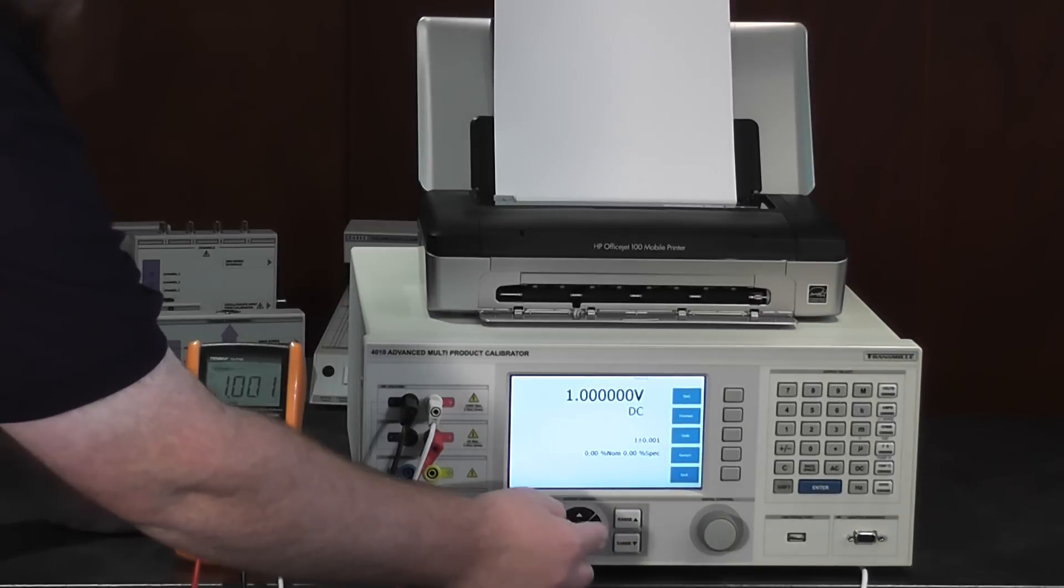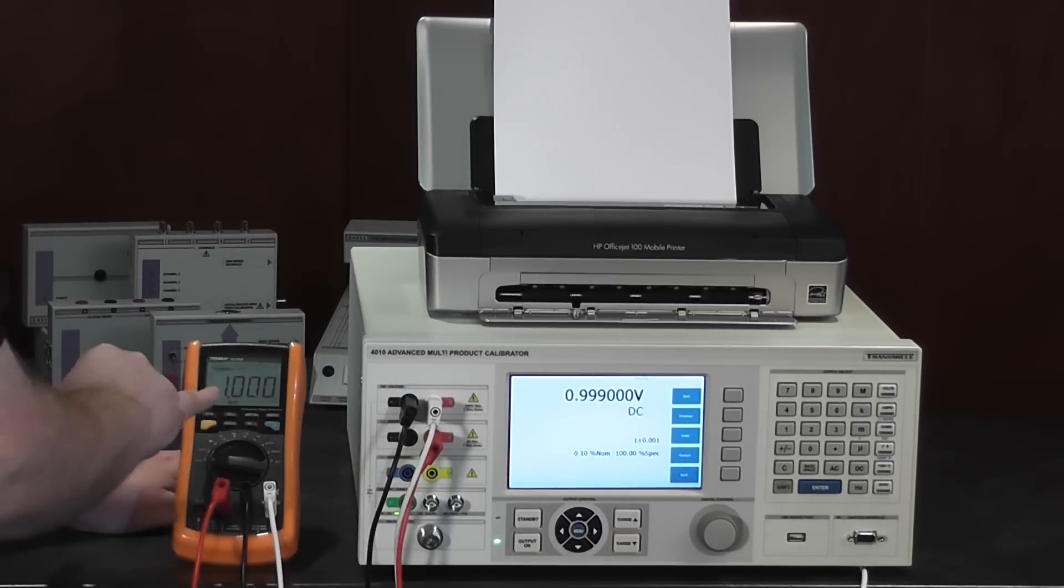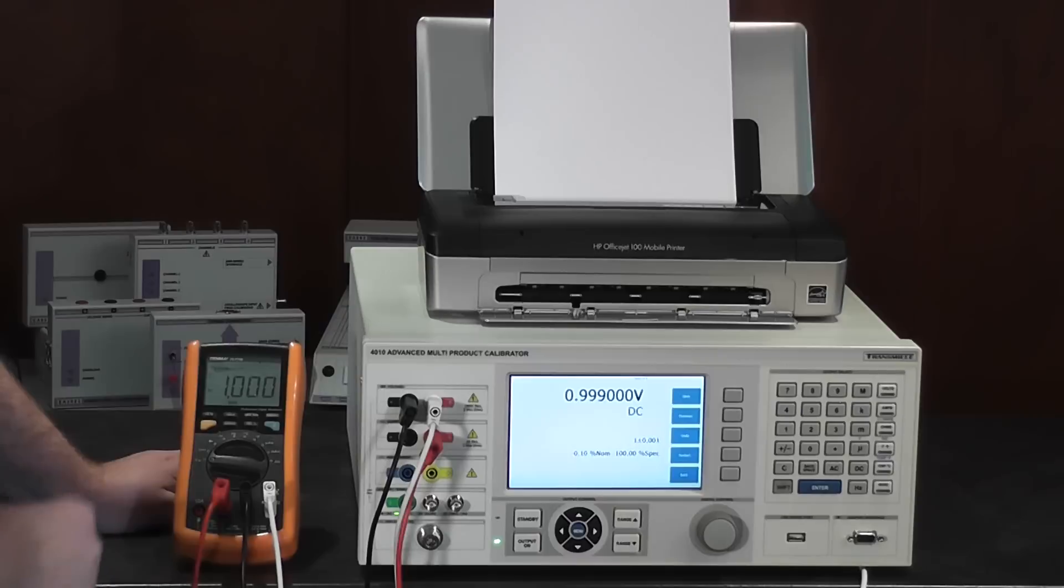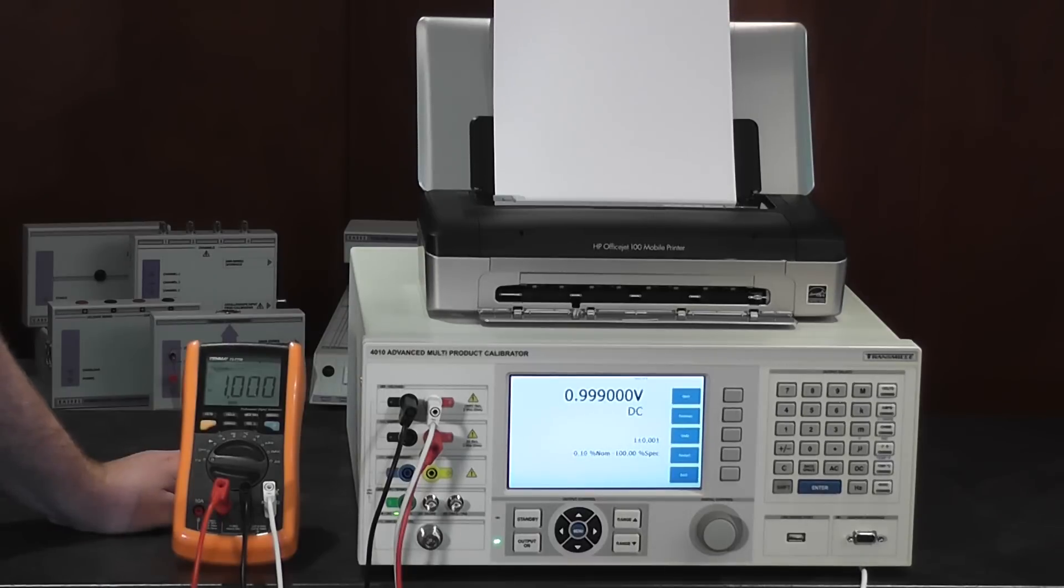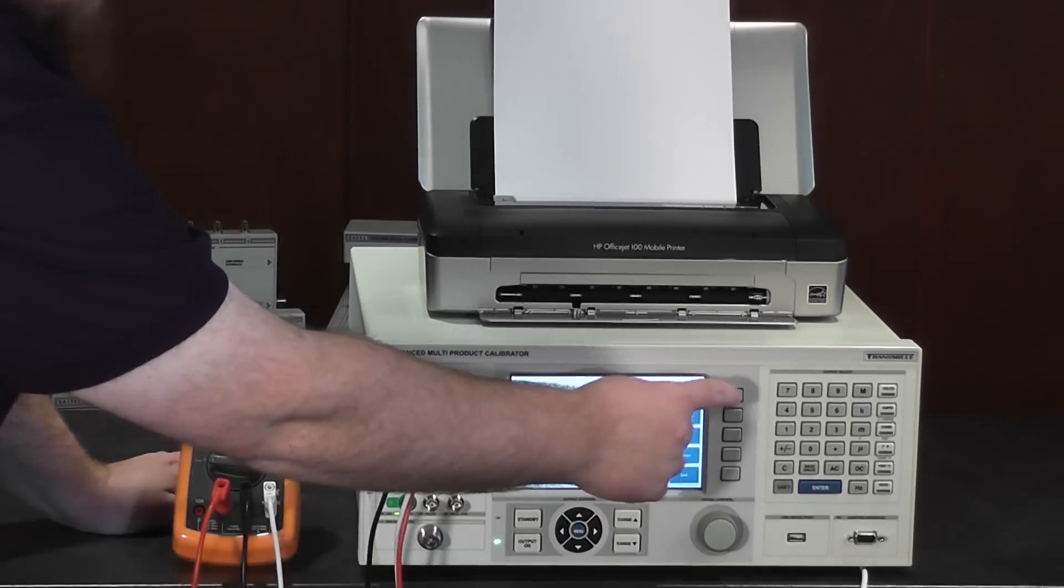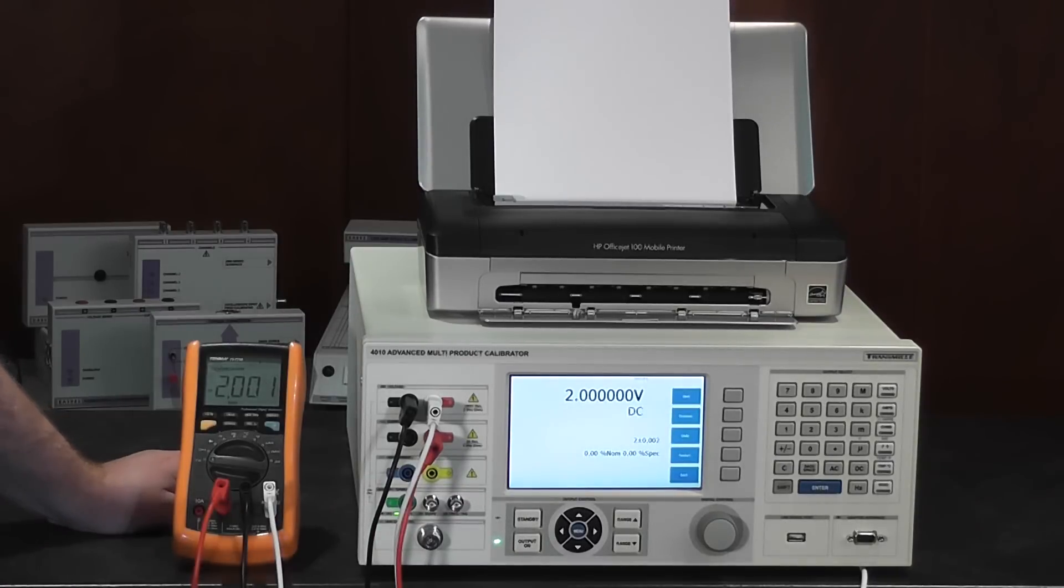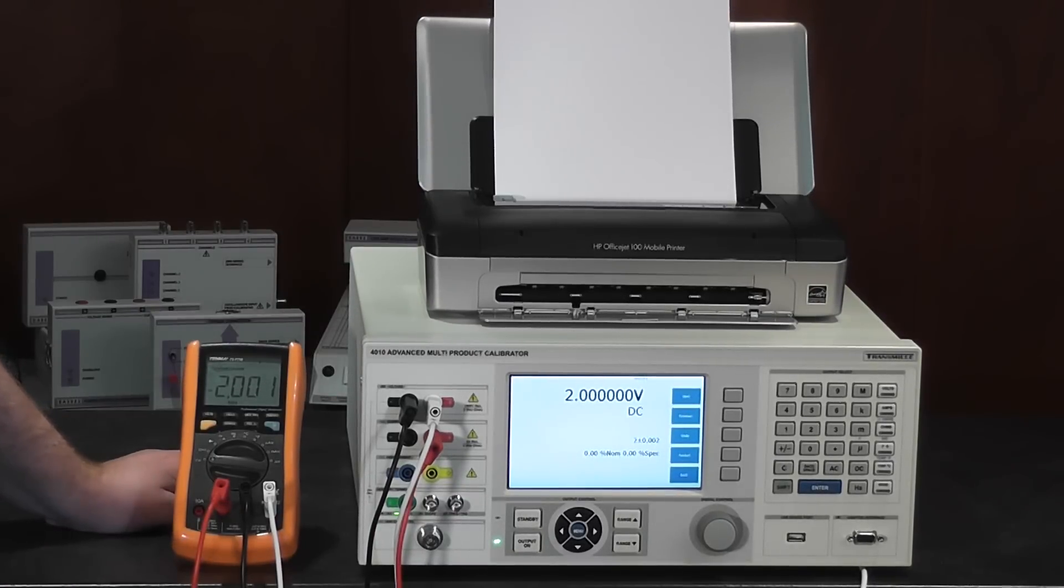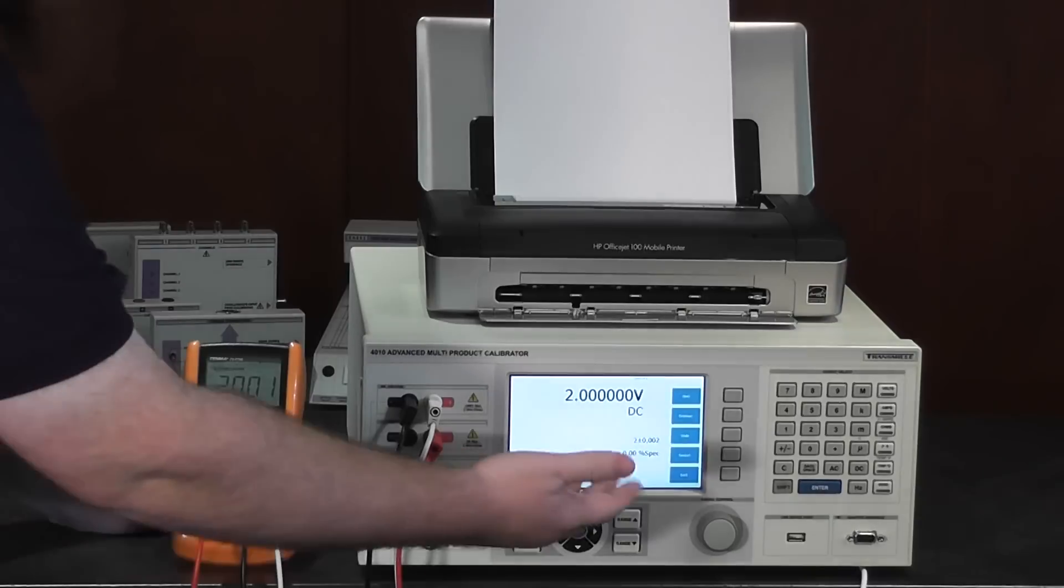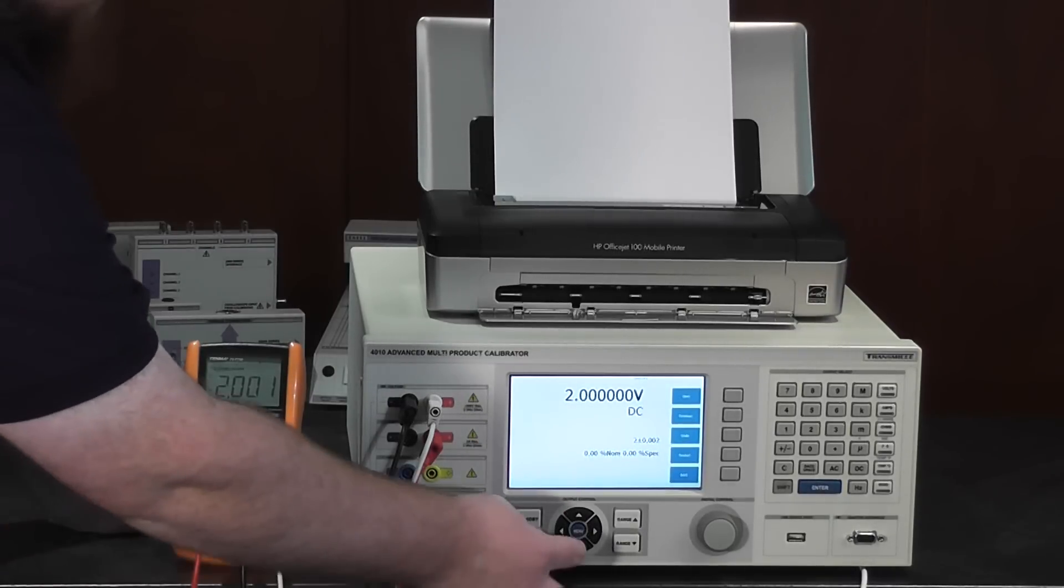...and deviate the output of the keyboard to get the correct measurement on your multimeter, and press next. The calibrator has stored the result, calculated if it's a pass or a fail, and then presented you with the next step.